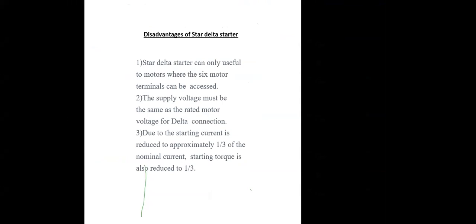There are a lot of disadvantages also. A star delta starter is only useful for motors where the 6 motor terminals can be accessed. Of course, it depends on ordering again. The supply voltage must be the same as the rated motor voltage for delta connection. That is also generally taken care of during ordering. During starting, as I said, it will take more time because the starting torque is also reduced with the voltage, because voltage and RPM are directly proportional.